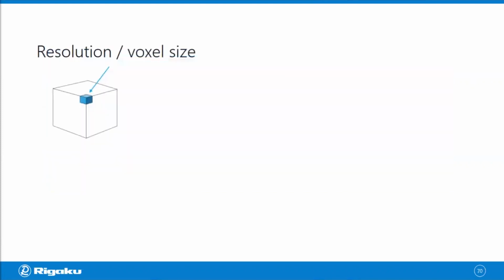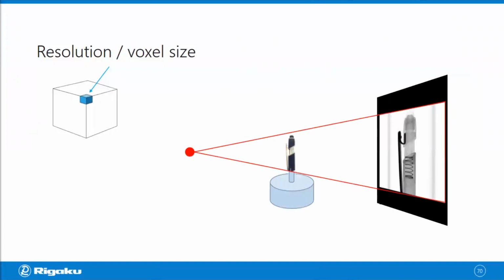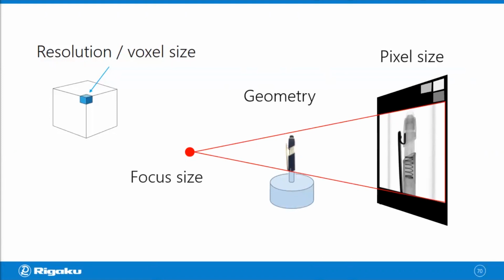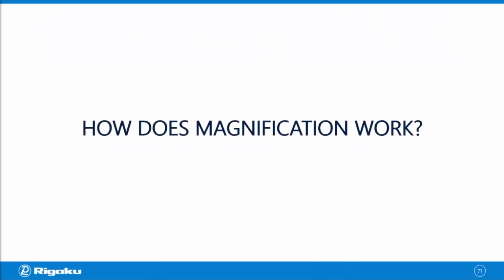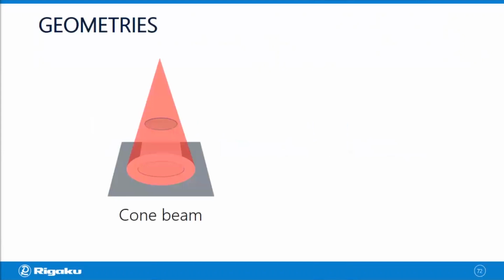Now let's take a look at the resolution and see what determines it. The resolution, or voxel size, depends on the focus size and the pixel size on the detector side, and also the geometry you use. Since X-ray CT scanners used for material science work as microscopes as well, there is some sort of magnification going on. And how does that magnification work? That depends on the geometry you're using.